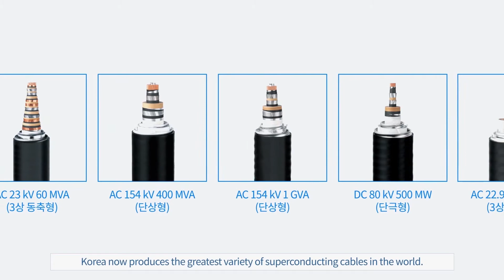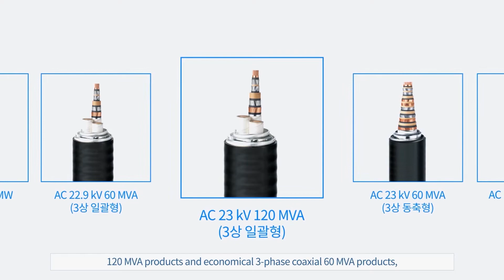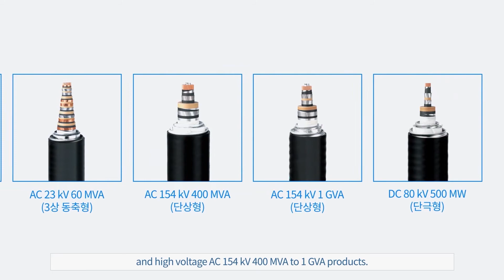Korea now produces the greatest variety of superconducting cables in the world. As for superconductive distribution cable systems, there are AC23 3-phase 60 MVA products, 120 MVA products, and economical 3-phase coaxial 60 MVA products, and high voltage AC 154 kV 400 MVA to 1 GVA products.